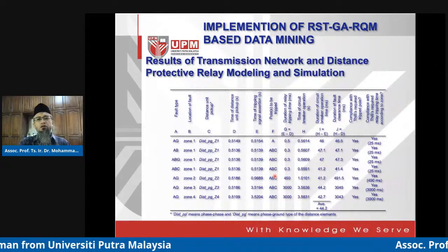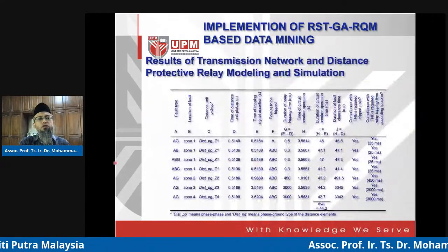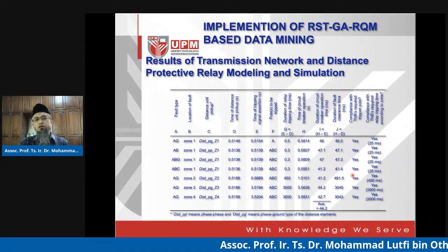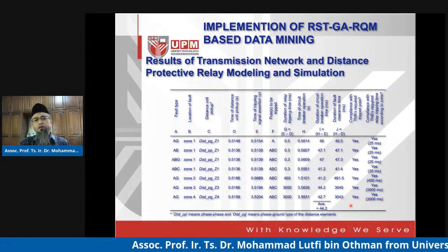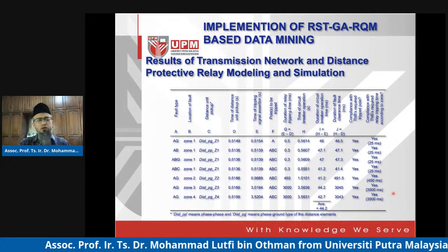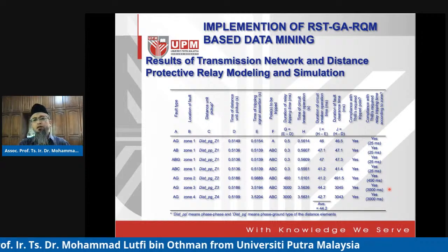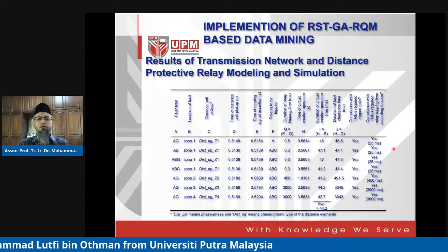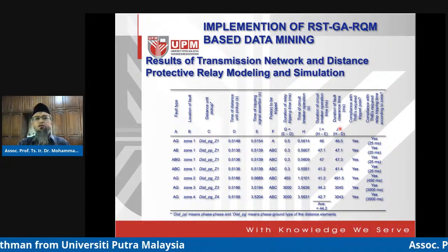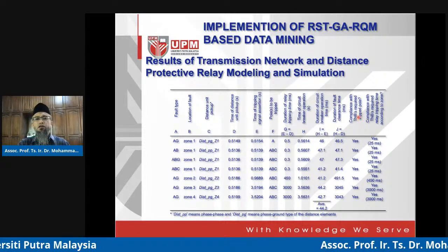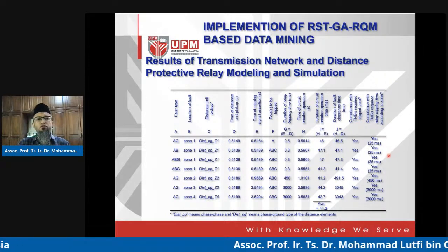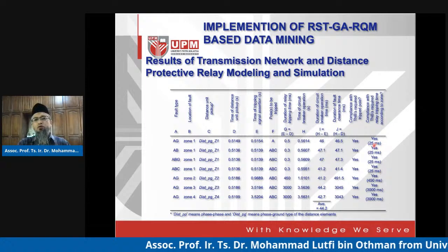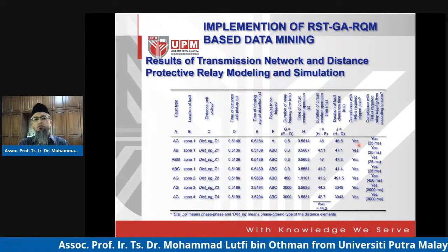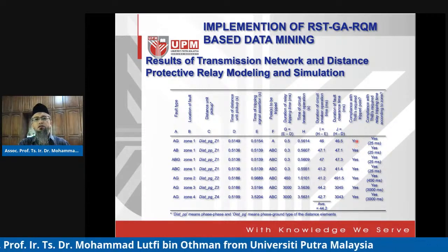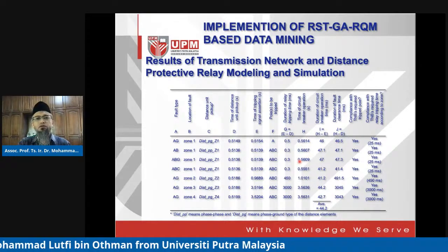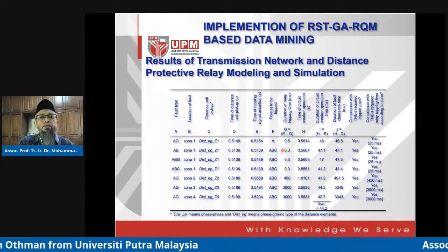So all in all, that's for one type of fault. You have so many other faults. As you can see here, the relay has successfully operated according to what is required by the standard operations of the required standards. For example, for zone 1, it has to operate in 25 milliseconds. Yes, it did so successfully, very much less than that. It's only 0.5 millisecond.